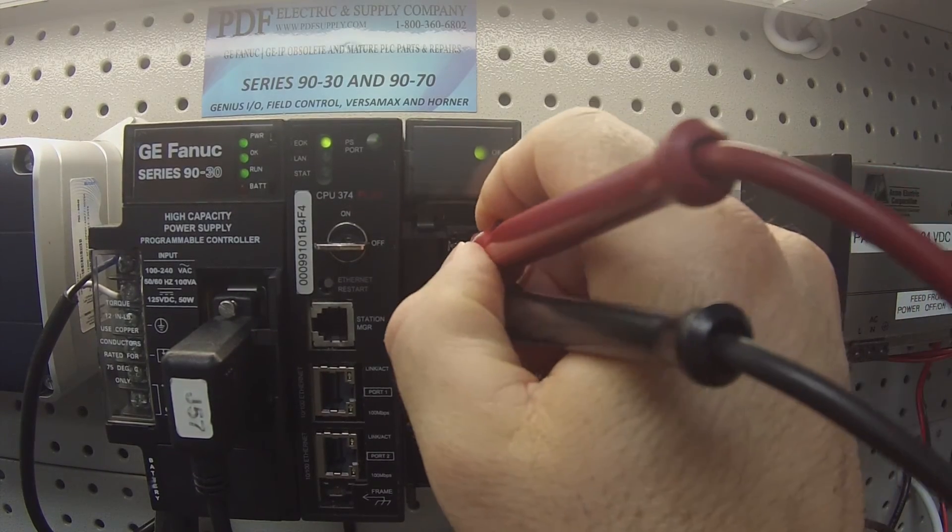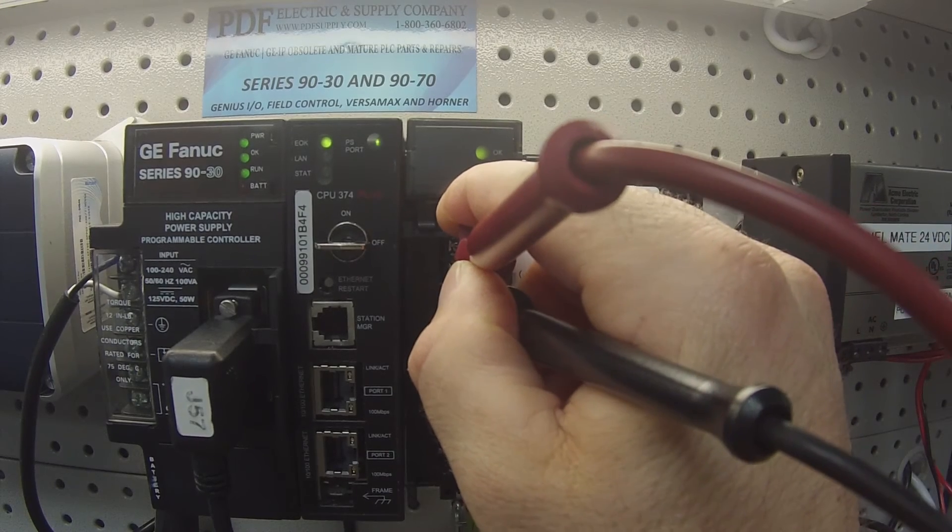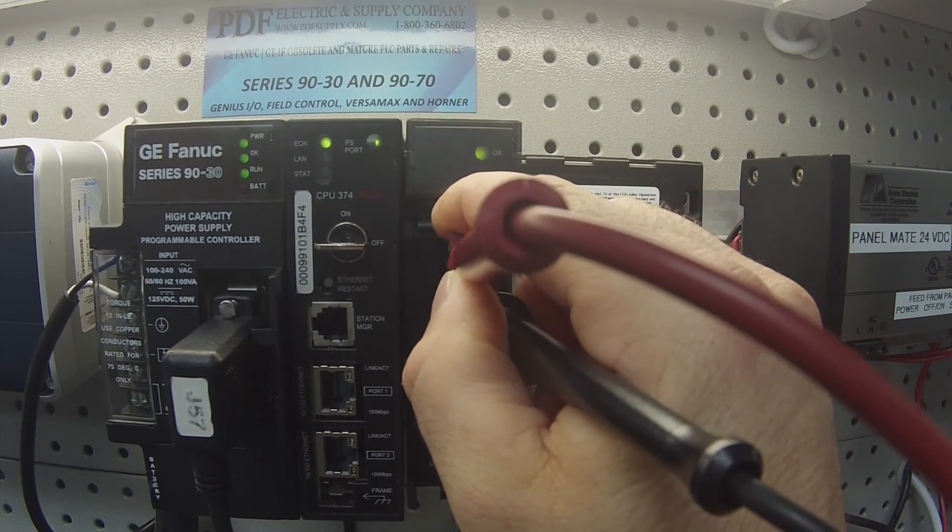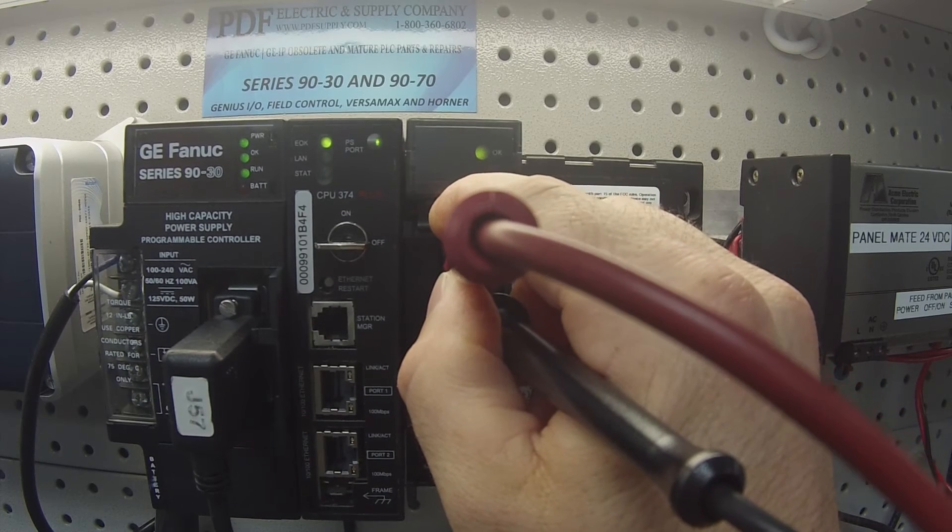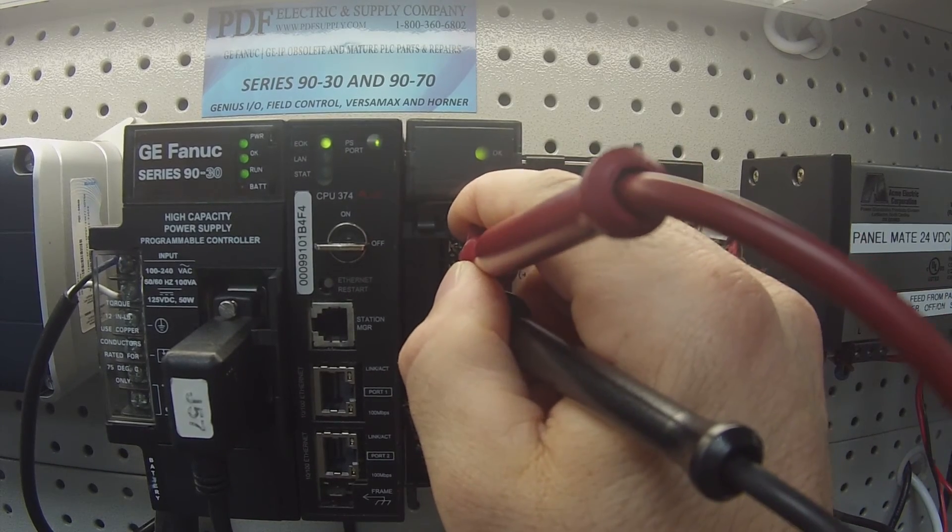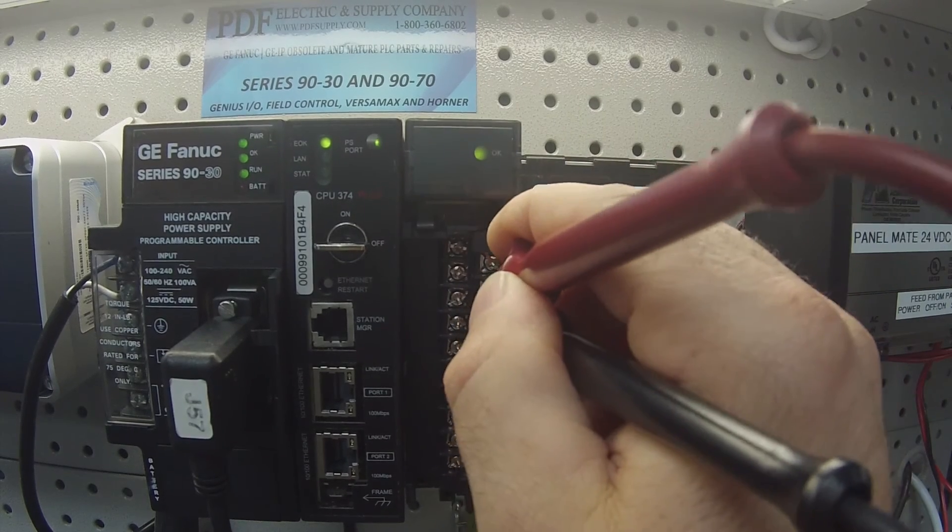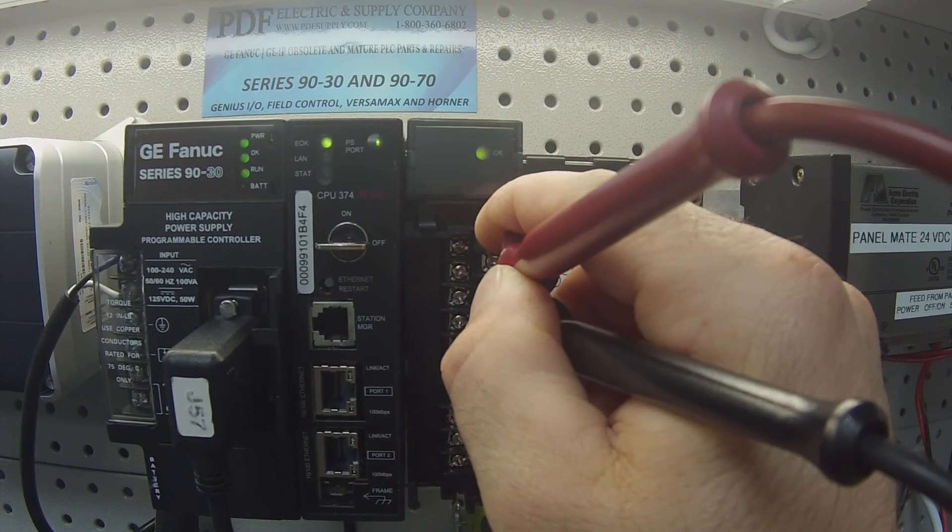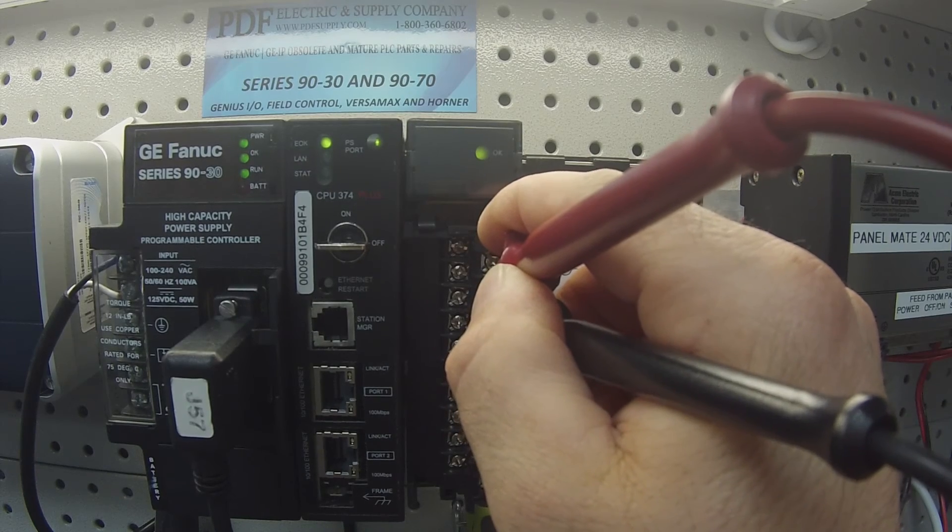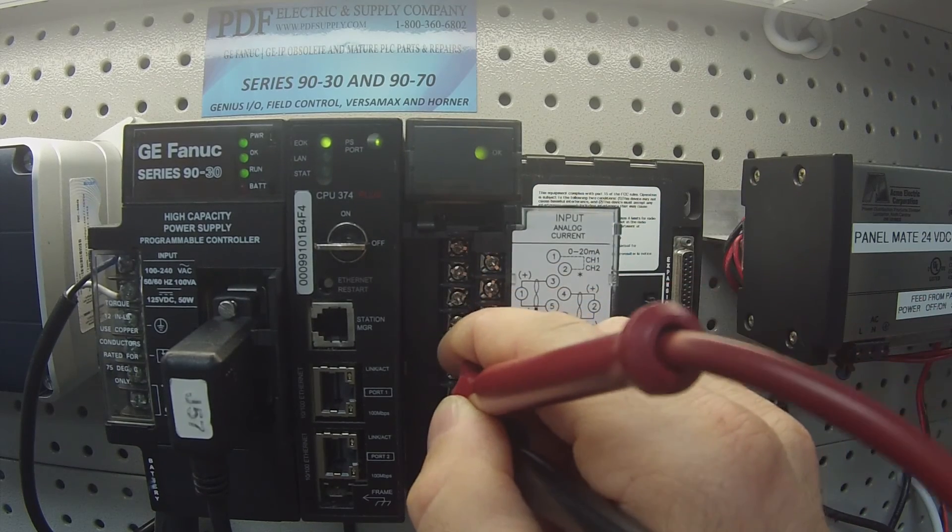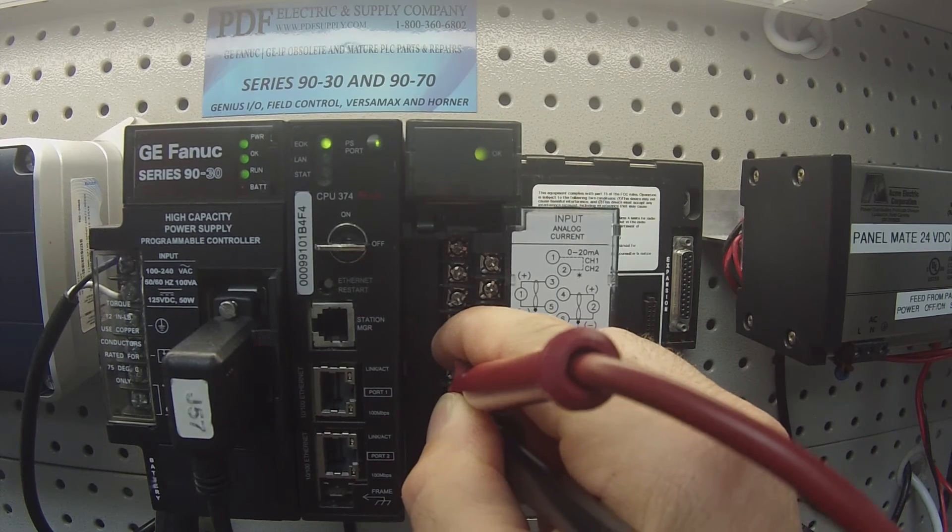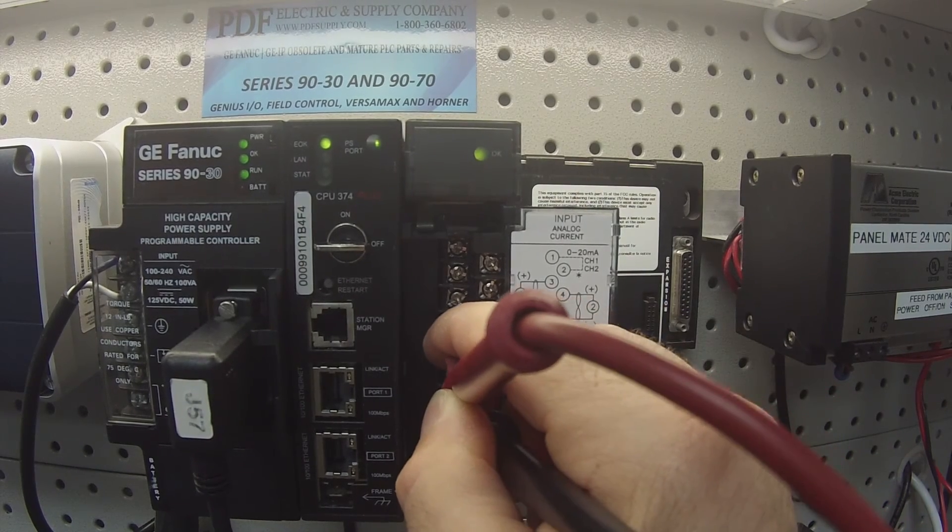What I've done is I've selected a value somewhere in the middle of 4 to 20 milliamps on the generator and not changed it so that I can test each channel with the same amount of current to make sure they all give me the same exact reading. I don't want a reading that is far beyond or below the reading that the previous channel has given me.